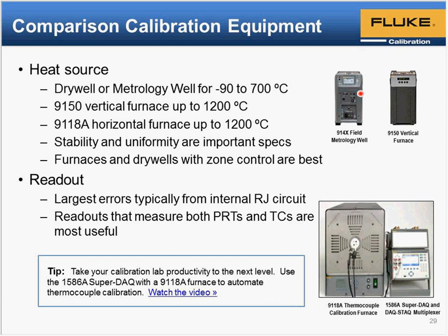For applications, there is this small portable high temperature thermocouple furnace that's popular for our thermocouple customers. But because it's so small and has such a large gradient, it's not an ideal instrument to use. But for high temperature applications, there are a lot of options. If you need better uniformity for high temperature applications, then you need to move toward a horizontal furnace, like the one shown in the lower right-hand picture. But furnaces have depth to them, so they really only accommodate longer thermocouples. The small little 12 inch long thermocouples that you see all over the place can't be calibrated in these furnaces. They're long enough to be calibrated inside these big horizontal furnaces.